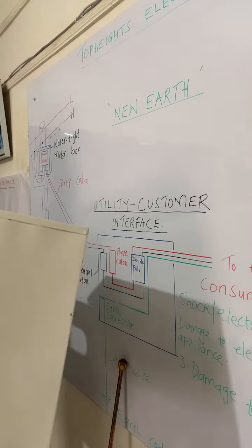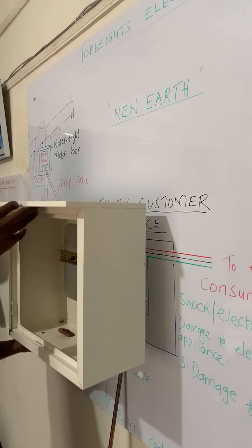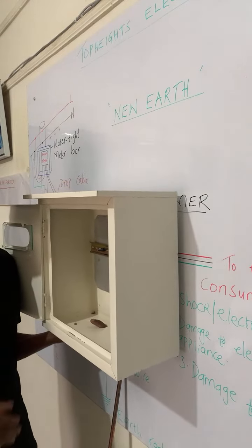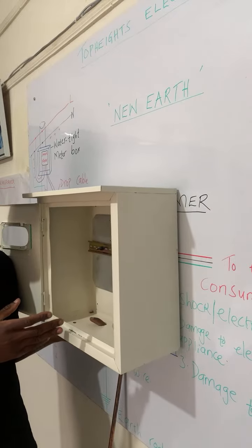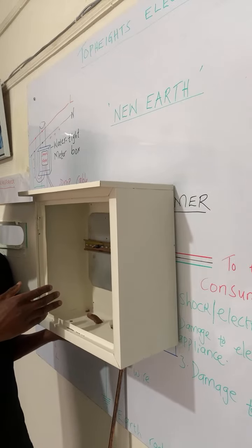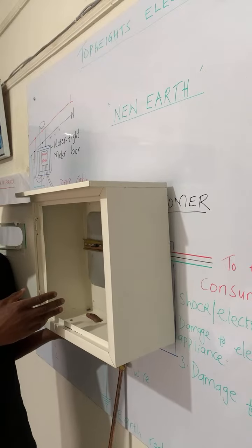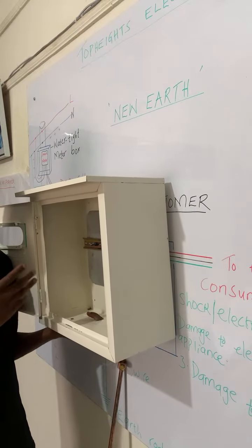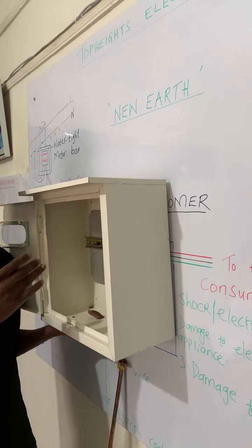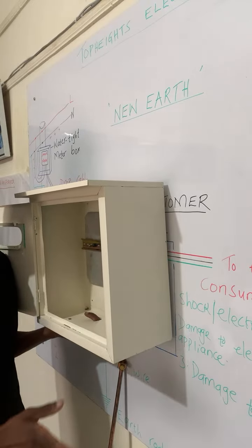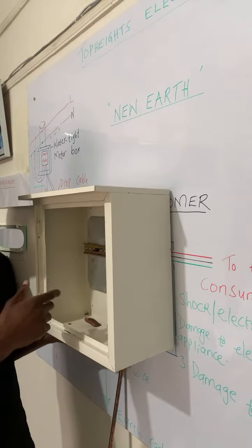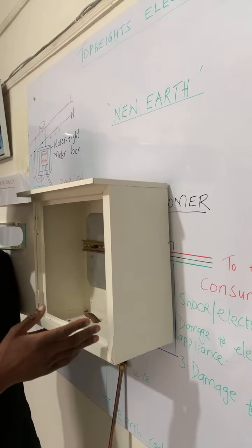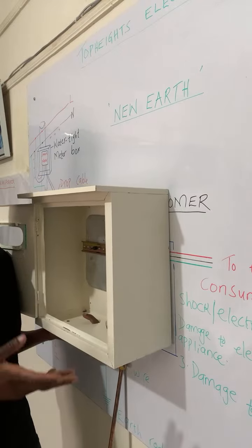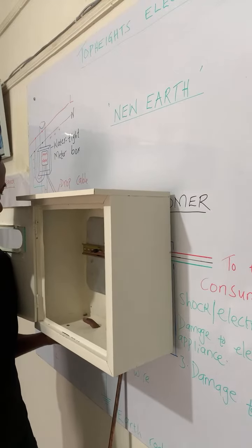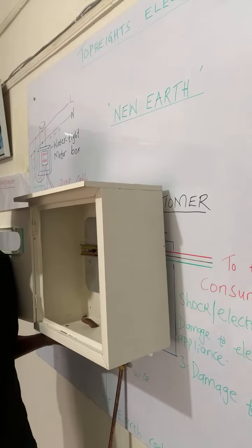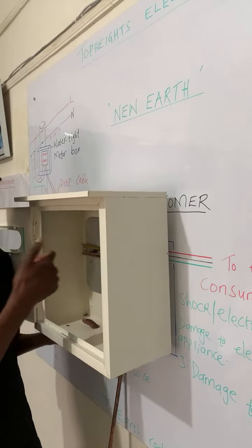So let's say we have our meter box here, and we will have our cutout just so we isolate the electricity in case of an issue. We can as well have the double pole. The purpose will be to isolate electricity in case of an overcurrent at the loads or a short circuit at the loads, or we just want to isolate electricity from that installation so that we may do either maintenance work or upgrading, or we are extending the electrical installation. We have to switch it off.